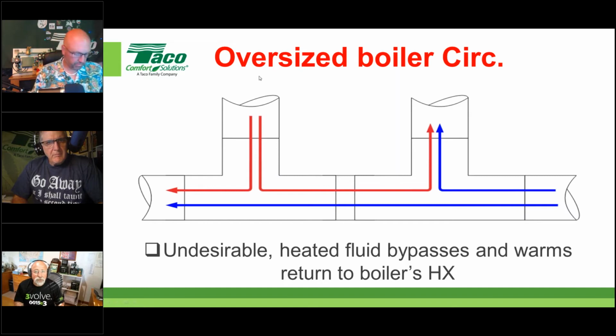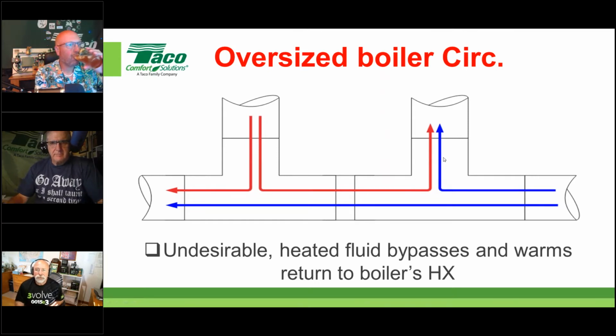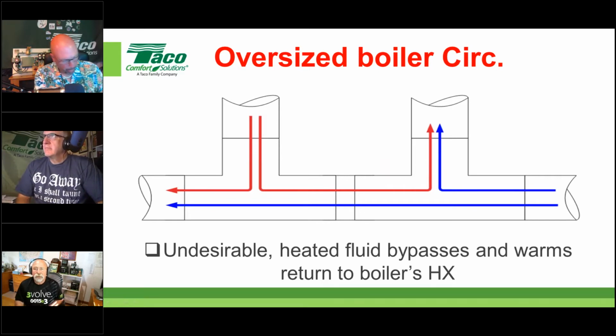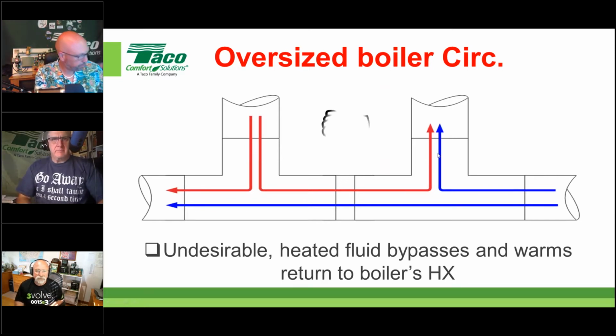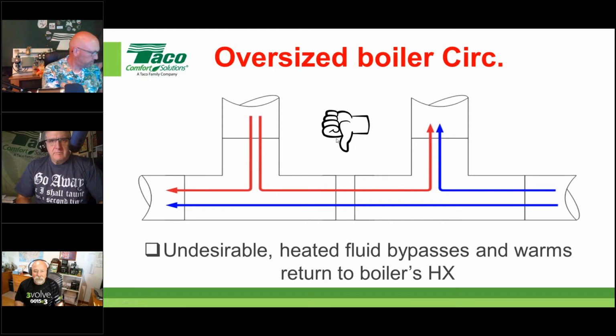So as I oversize the boiler circulator, I'm going to bypass, and some of that is not going to go all the way out of here because of hydraulic isolation, right? I'm going to come right across the top of these two T's, and I'm going to warm the water going back to the boiler, which is not a good thing if we're trying to obtain the lowest temperature coming back to the piece of equipment. Okay, so I'll give that a thumbs down for you there. So hopefully that concept makes sense to you.